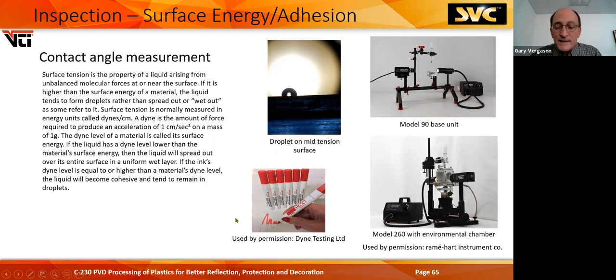And these are good tests for having on the production floor, although these pens have a pretty short shelf life. But if you've got an adhesion problem for your PVD coating, you can use these pens to see what that surface dyne is. And that's how you dial in your etching prior to your PVD. And then Rame-Hart Instrument Company makes this base model of a contact angle system. And this one's a little fancier, with an environmentally controlled chamber on it for looking at higher level stuff.